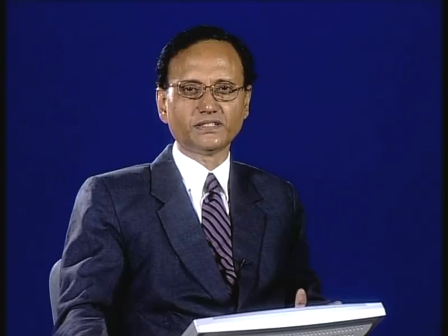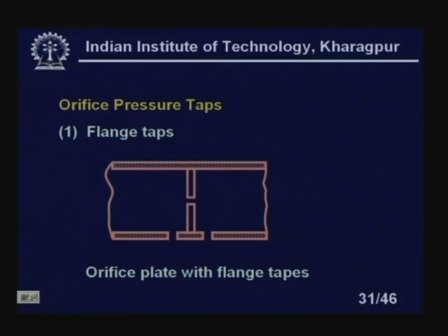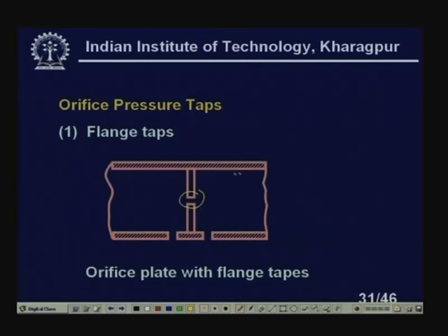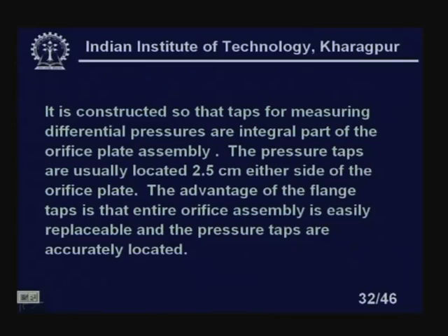There are various pressure taps available for the orifice. In this lesson we discuss three: flange taps, D and D/2 taps, and vena contracta taps. Flange taps are constructed so that the taps for measuring differential pressure are an integral part of the orifice assembly, usually located 2.5 cm either side of the orifice plate. The advantage of flange taps is that the entire orifice assembly is replaceable and the pressure taps are accurately located.